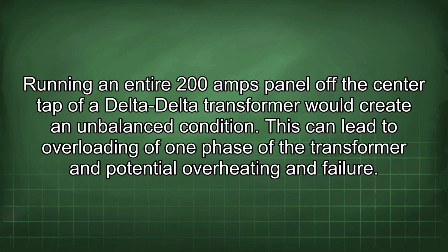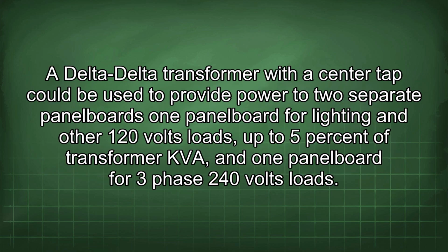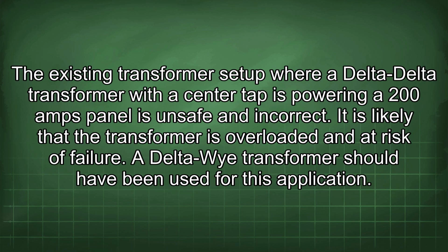Running an entire 200 amps panel off the center tap of a delta-delta transformer would create an unbalanced condition. This can lead to overloading of one phase of the transformer and potential overheating and failure. A delta-delta transformer with a center tap could be used to provide power to two separate panel boards, one panel board for lighting and other 120 volts loads, up to 5% of transformer kVA, and one panel board for three-phase 240 volts loads. The existing transformer setup where a delta-delta transformer with a center tap is powering a 200 amps panel is unsafe and incorrect.